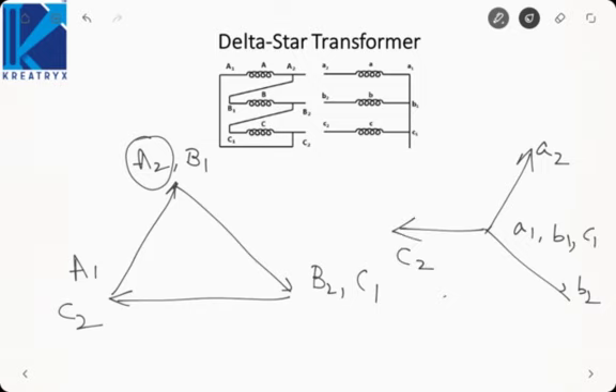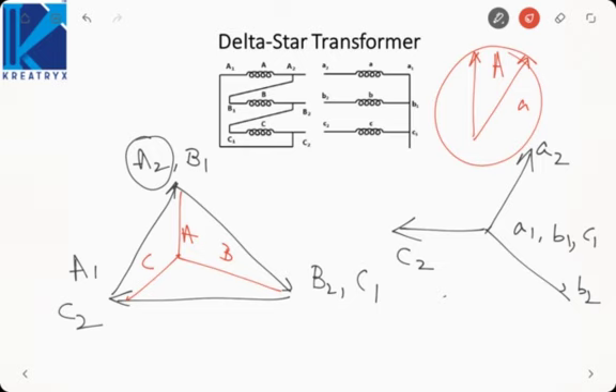So if we plot it on a clock, first of all we will need reference phasors A, B, C. A is vertically upwards, small a is like this. So it is as if 1 o'clock is the time, so it will be Dy1. So it provides a 30-degree lag. So we have seen that this transformer can provide 4 types of phase shift: plus minus 150 degree and plus minus 30 degree. These are the possible phase shifts with the delta star connection.